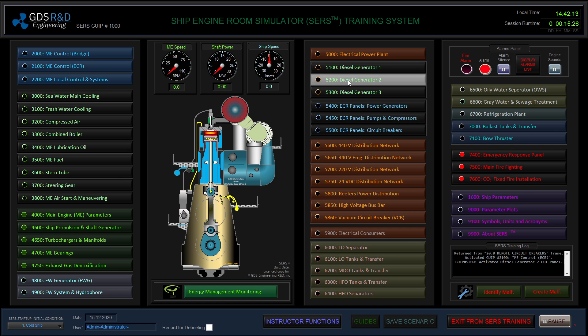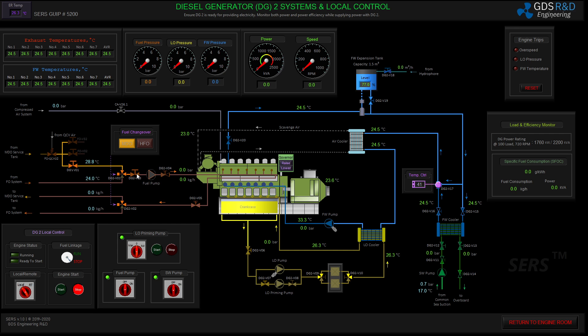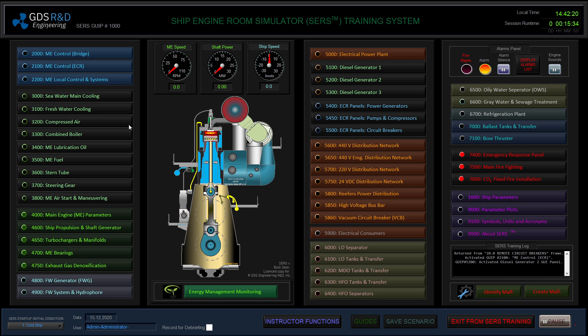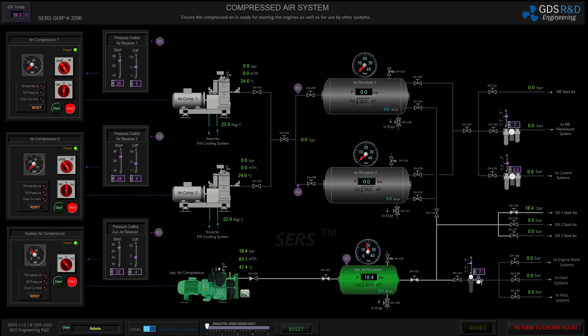Now I will start diesel generator two and perform the parallel run of the two diesel generators. But first I would like to check my compressed air — there is about 18 bar of pressure. I will stop the auxiliary air compressor and supply that start air pressure to diesel generator number two.